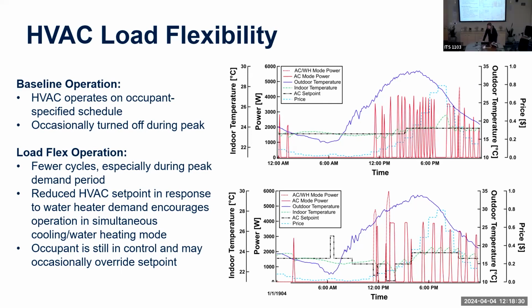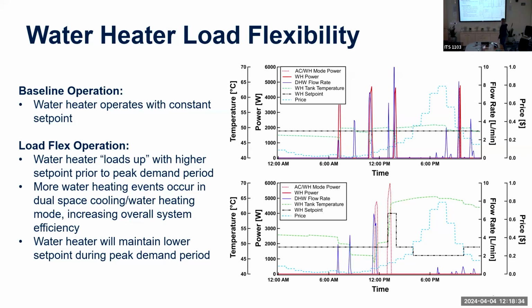Moving on to water heater load flex. This is the same day, just an example — we'll look at a multi-day case to get a better idea of how it looks long-term. For the water heater baseline, we operate with a constant set point, and for load flex it's the same set points shown before. Right before 12, that's the water heating event that called for the reduced set point in the HVAC system, inducing that dual HVAC and water heating event, so there are more of those because of our control sequence. This particular day had no water heating use because of the elevated water temperature going into the peak demand period, though that can change based on water demand that day. That's why we'll look at it over a multi-day period.